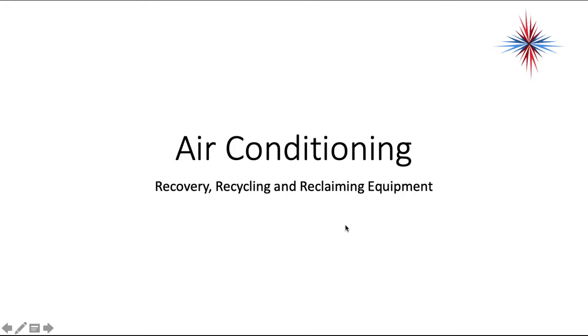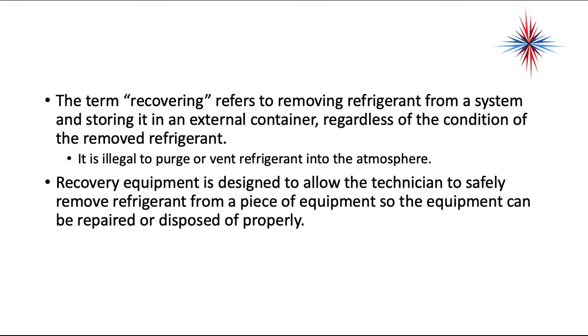In this video, we're going to be talking about the recovery, recycling, and reclaiming equipment, and a little bit about those three terms. These terms are considered the three R's of refrigeration and refrigerant handling. The term recovering refers to removing refrigerant from a system and storing it in an external container. This is regardless of the condition of the removed refrigerant. Note, it is illegal to purge or vent refrigerant into the atmosphere. There's some pretty heavy fines on that.